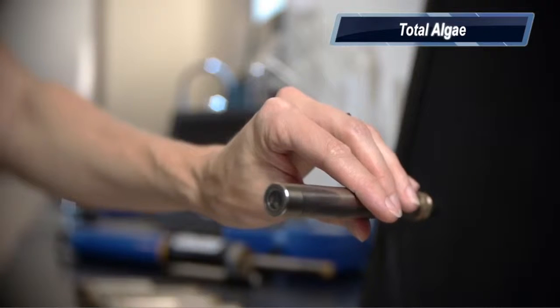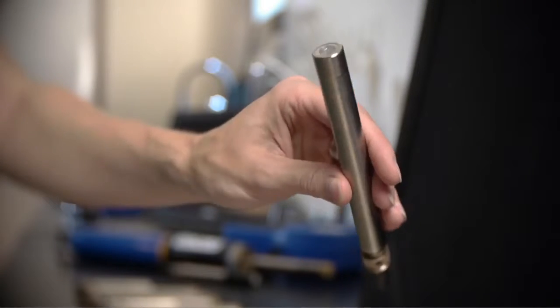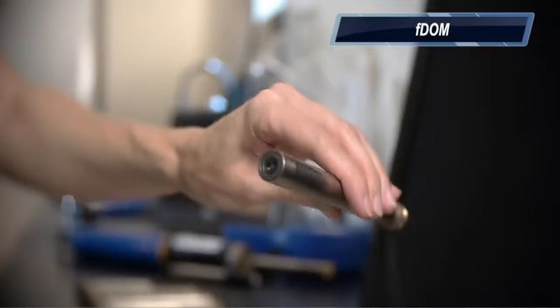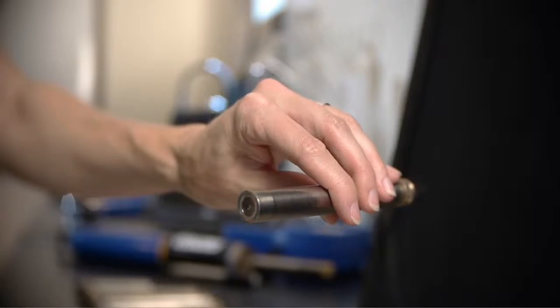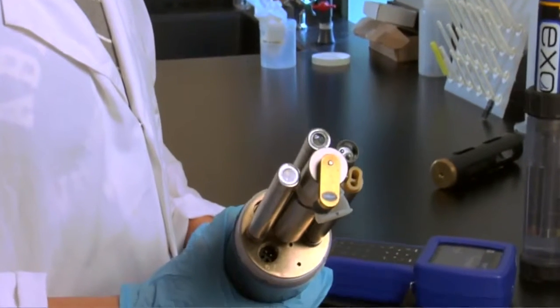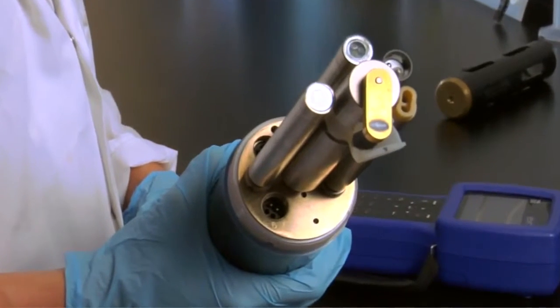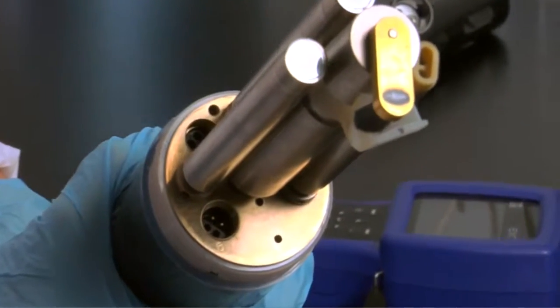People may be surprised to hear that we have two new sensors available for the EXO platform. Our total algae sensor, which combines algae measurement and blue-green algae measurement into one single probe, and also our FDOM sensor, which is new to YSI. The thing that the customers seem to be most surprised about is the ability to load multiple sensors of the same variety onto the sonde and perform the calibrations at the same time, which allows them to save a ton on calibration solution. So one of the biggest things is time savings in the field.